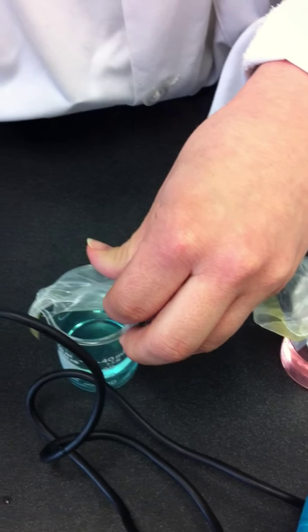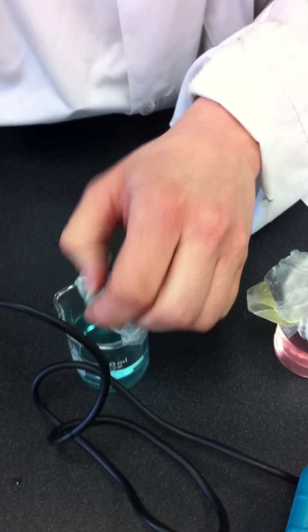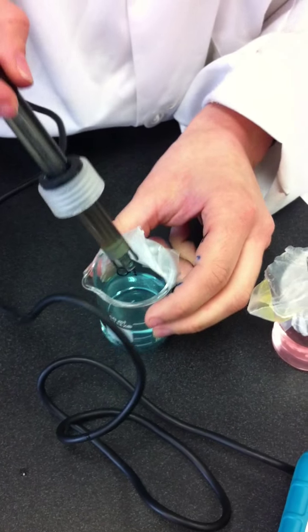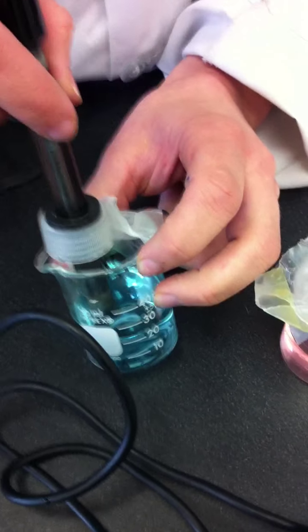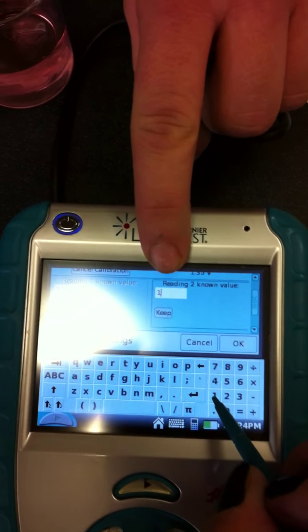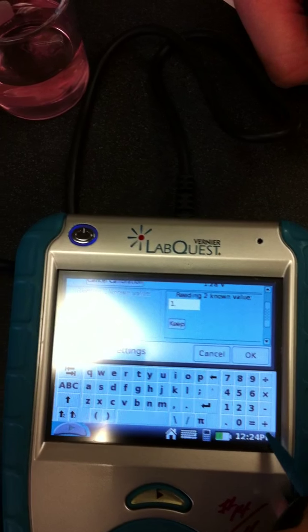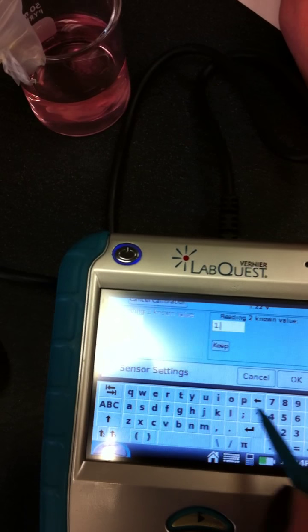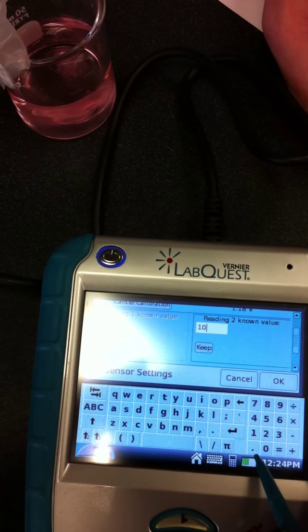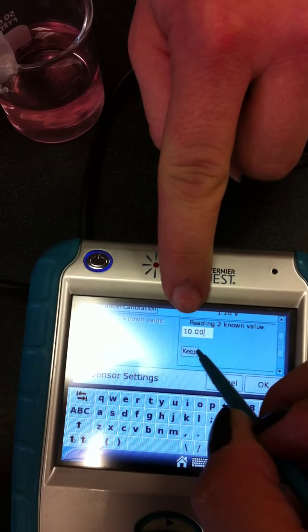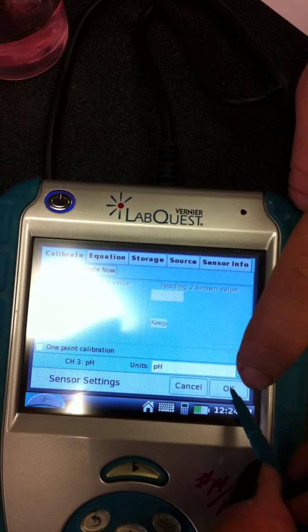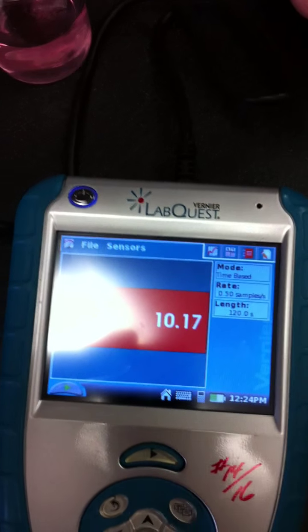And then we're going to go into pH 10 and tell the machine that this is a pH 10. Now, if we calibrate with these two range of pHs, then every pH thereafter should be correct. So now I'm in the 10. So now reading 2, you're going to tell the machine that this is a pH 10. 1, 0. So I'm telling it pH 10 and then push keep. And then we're finished. We've put 2 readings in, and it's enough for calibration.